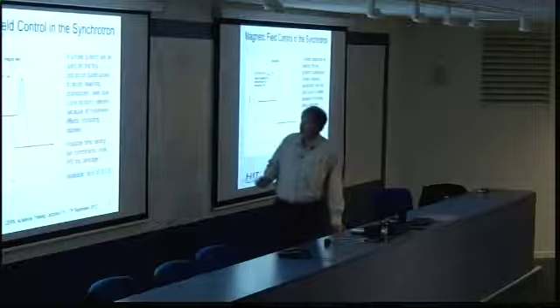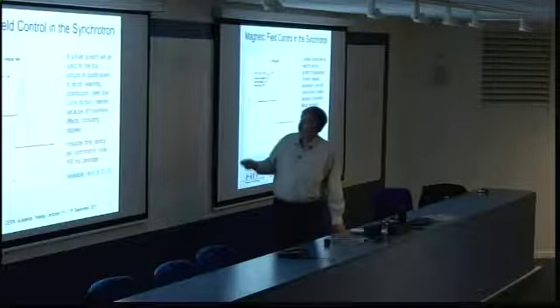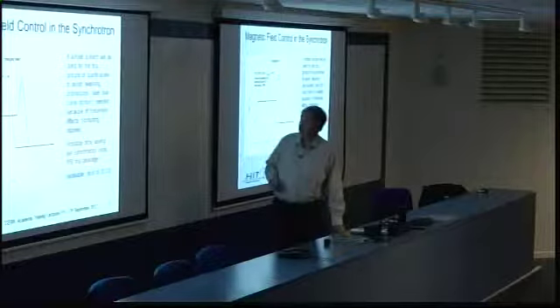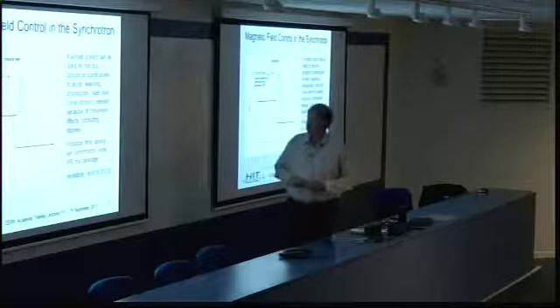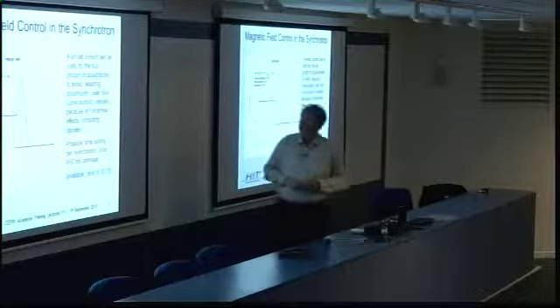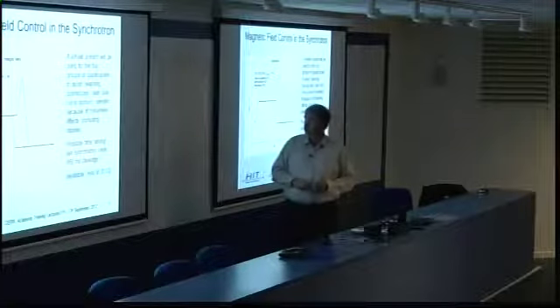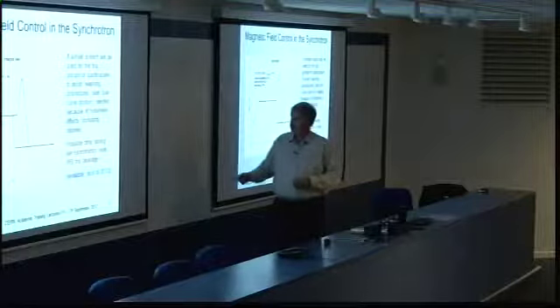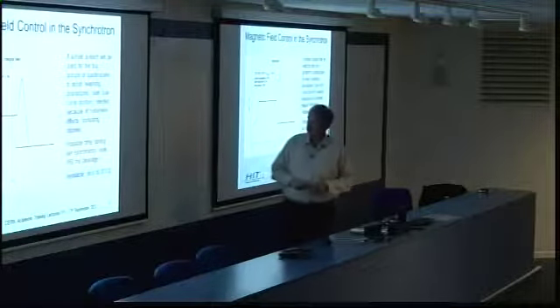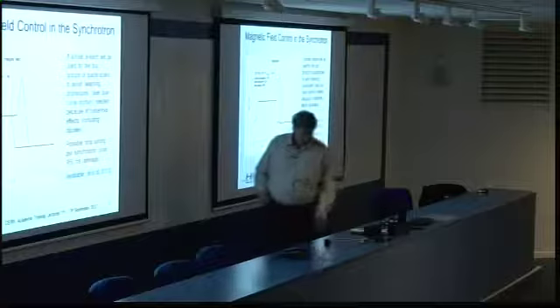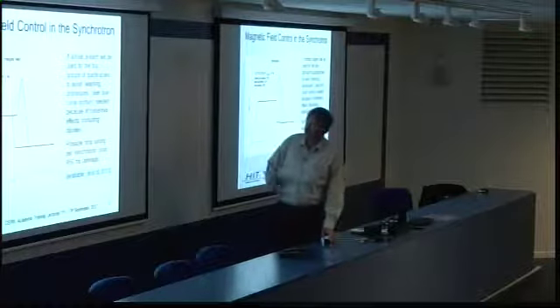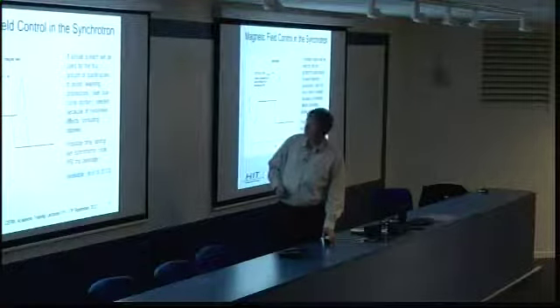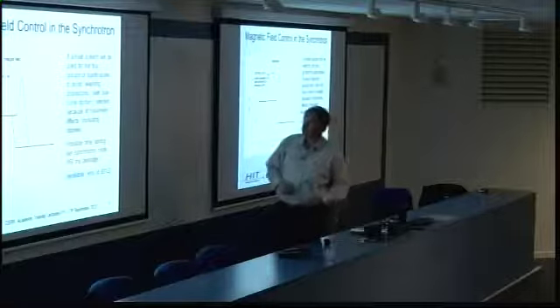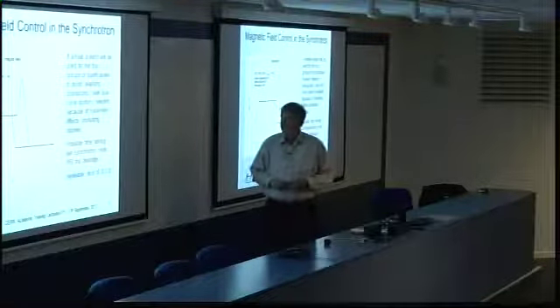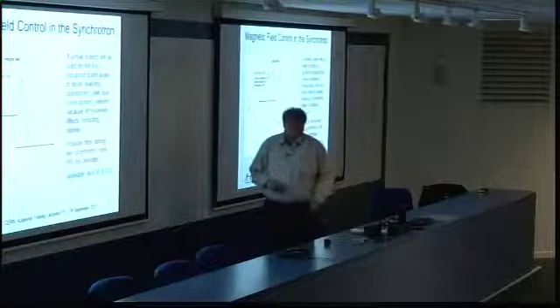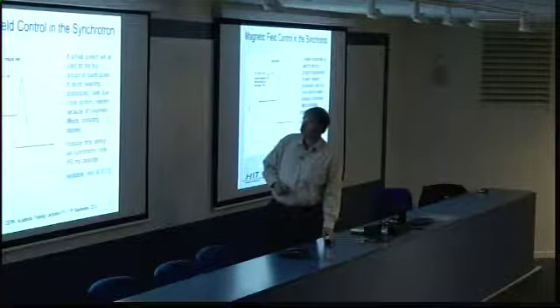We are working on these magnetic field control systems now for the 4 groups of quadrupoles inside the ring. It's a little bit more delicate than for the dipoles, but nevertheless we are sure that we can put it into operation at the end of this year, and that this would save a lot of time. So to get rid of dead times is really a struggle, but it makes sense because it minimizes the irradiation time, and especially the patient feels more comfortable if it's shorter than today.